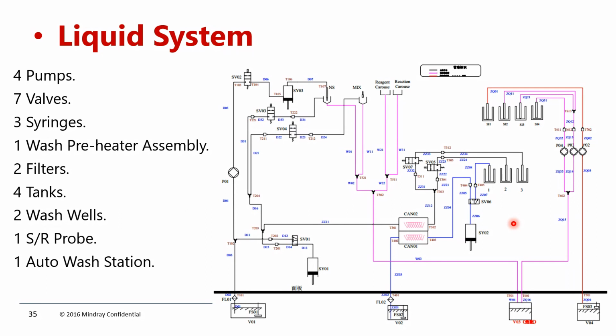Coming to the sequence, as we discussed, this instrument is wet chemistry. In this wet chemistry we are using semi-disposable cuvettes, meaning they have a limited specific period of time. As per the manufacturer, we replace all the cuvette segments once in 3 months. In this model we do not have a permanent cuvette system, not in BS-240. If you go to the higher end models, you have individual cuvettes. There also you have 2 types of cuvettes.